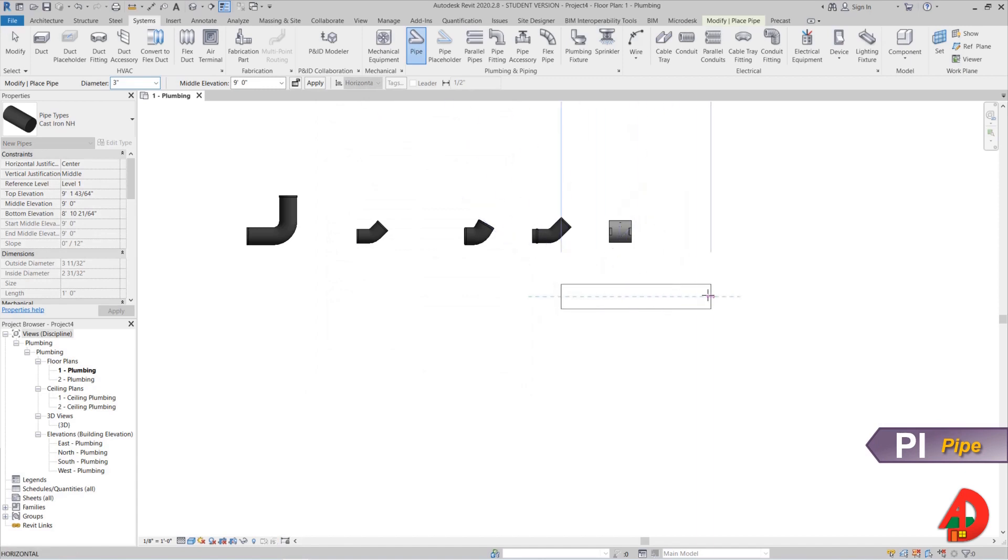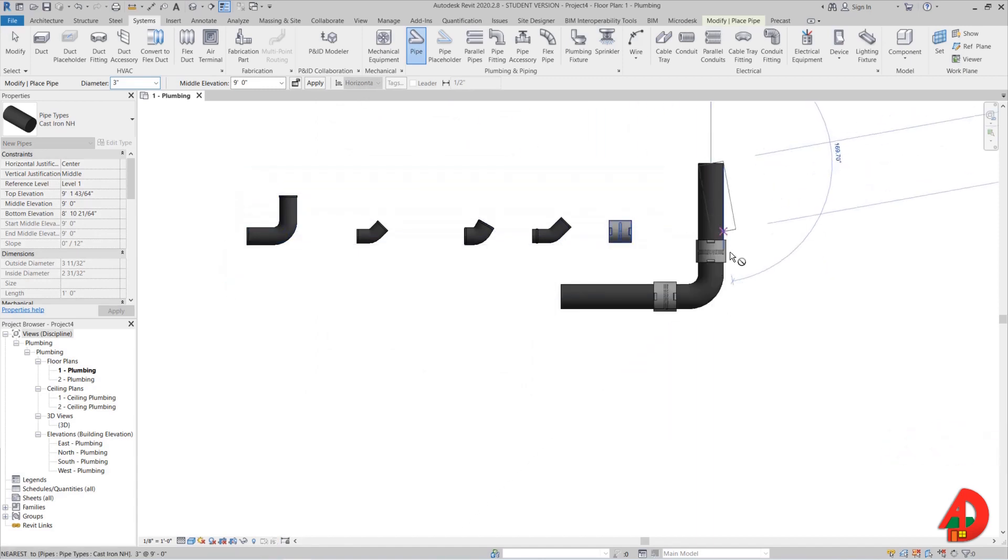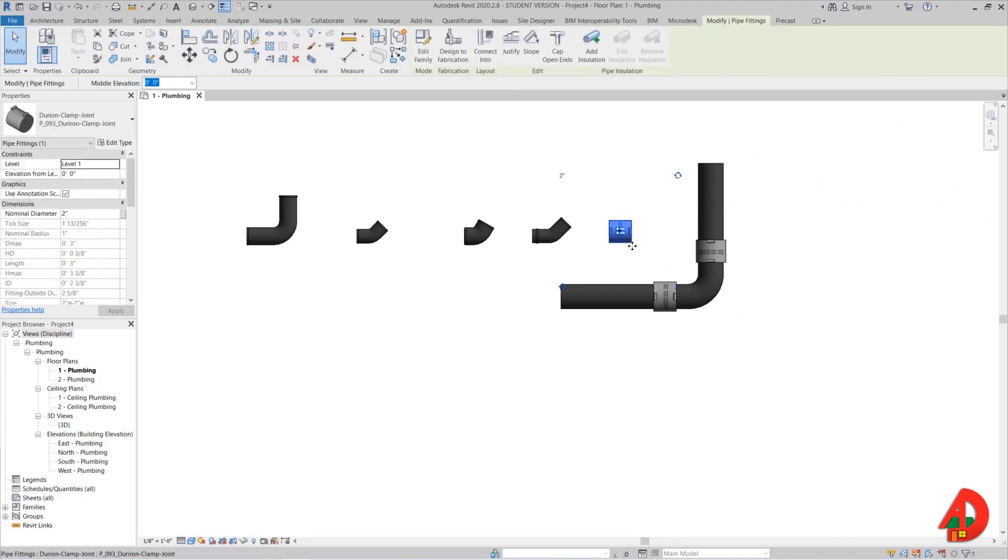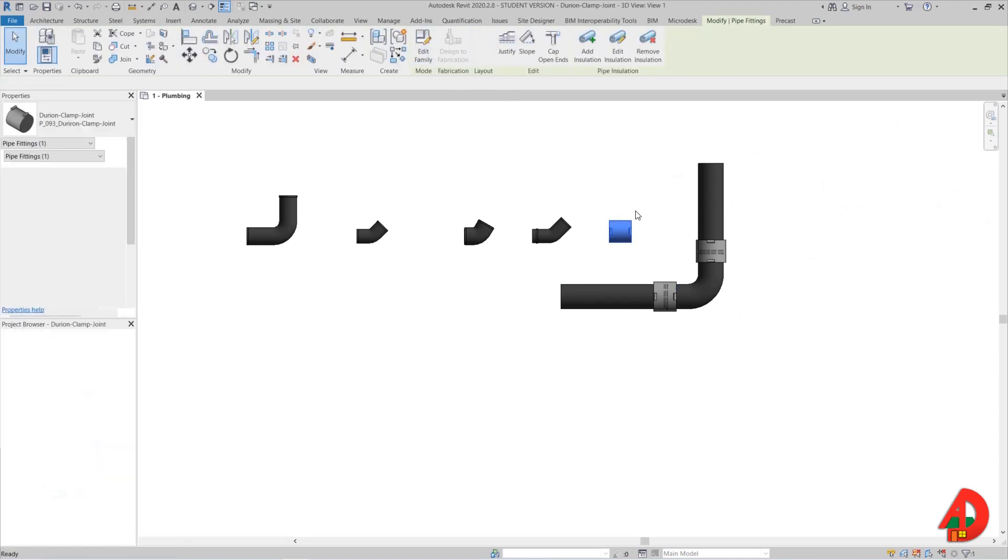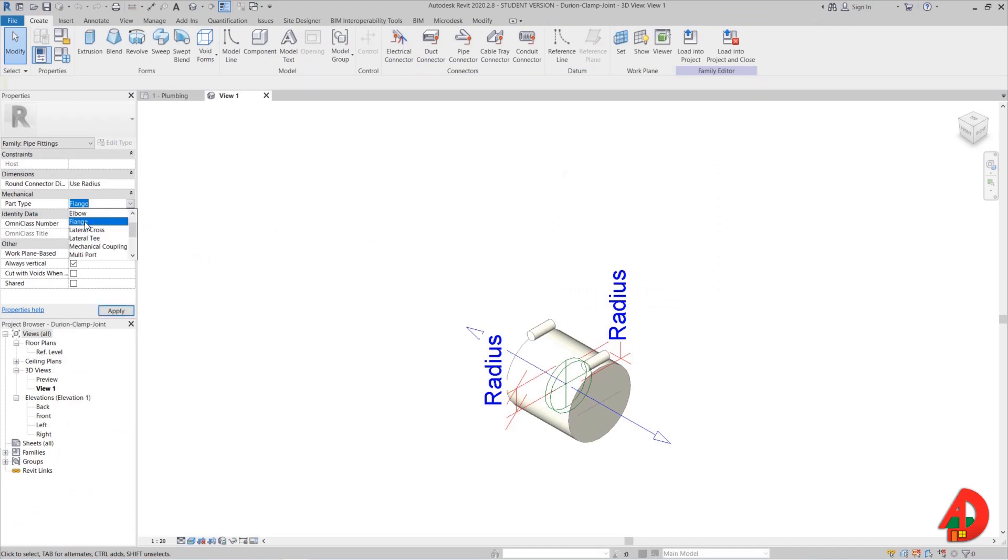Now since I am done with creating a new pipe and assigning my fittings that I need for now, I can start drawing a pipe and I will make a 90 degree bend. If you have problems finding the clamp in the flange routing preferences, you need to make sure that when you edit this family, here under part type there is a drop down menu, and in order to work it has to be defined as a flange.